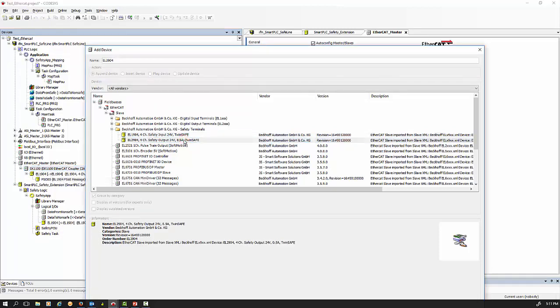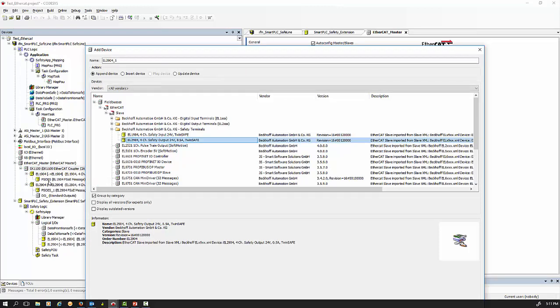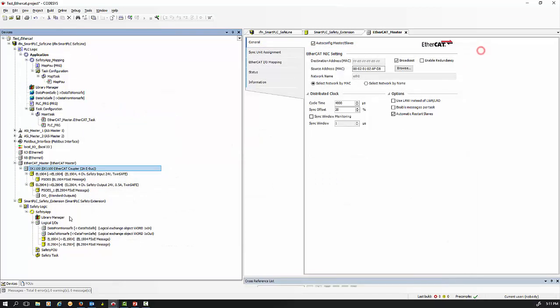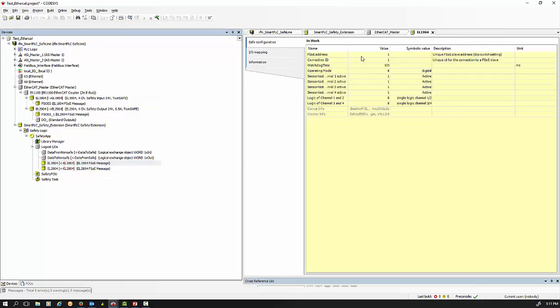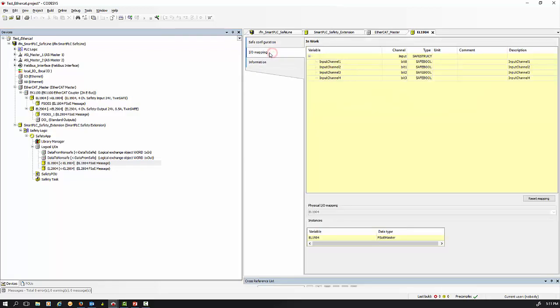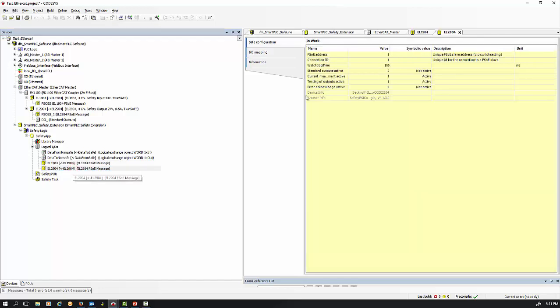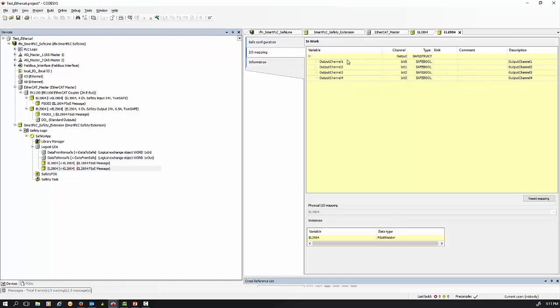Then add the output module, which will also add automatically in the appropriate section. For this case you don't need to do anything else on your non-safe PLC. If you double-click on your safety input module, there are a couple of addresses and connection IDs that are important. It will also automatically name your channels — channel input 1, 2, 3, and 4 — and do the same for the outputs, automatically generating variables.